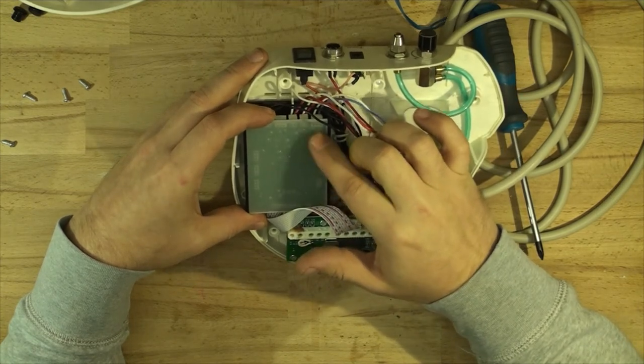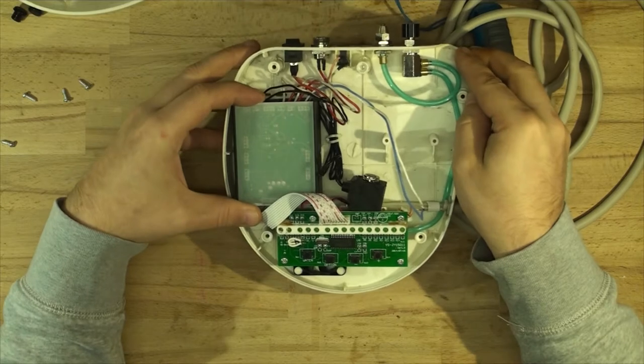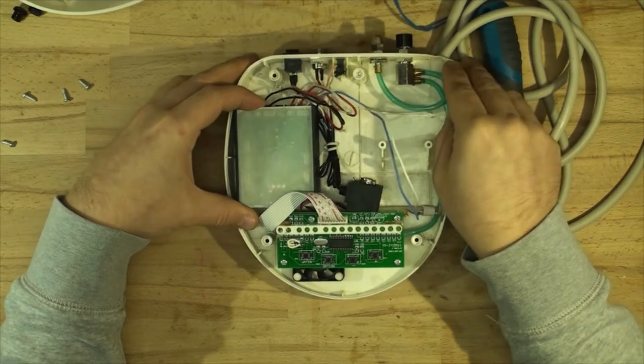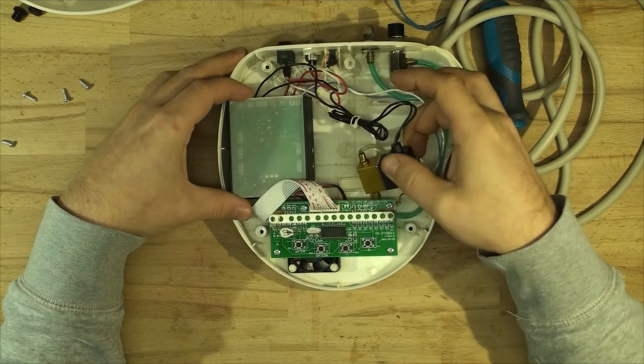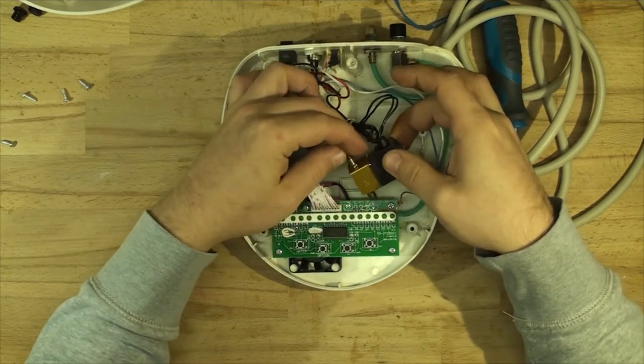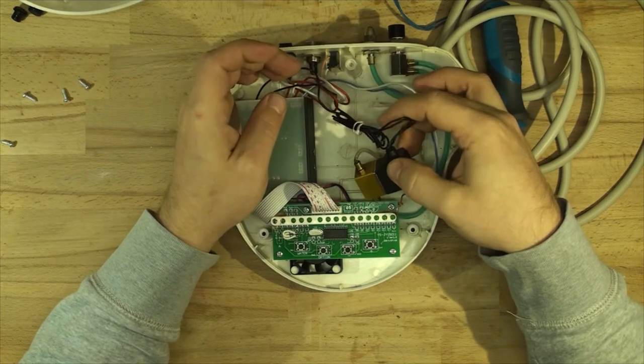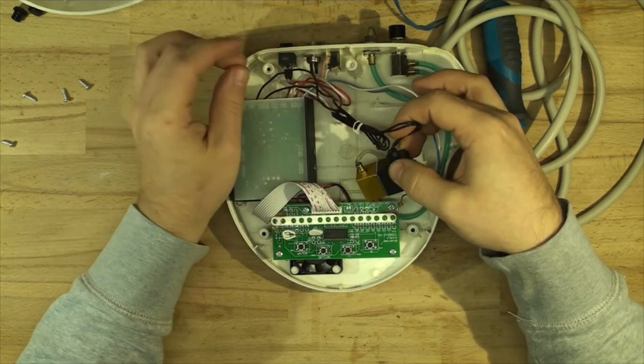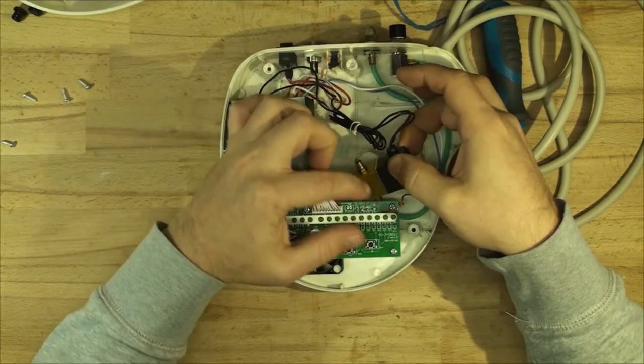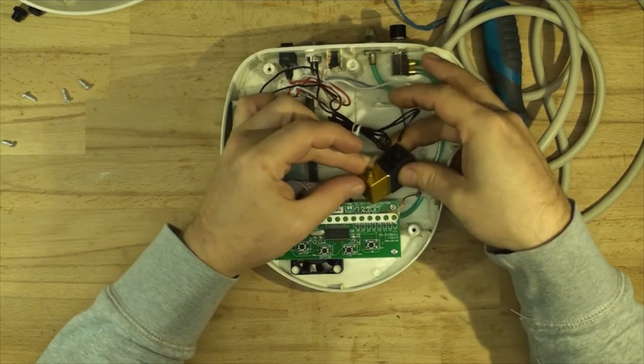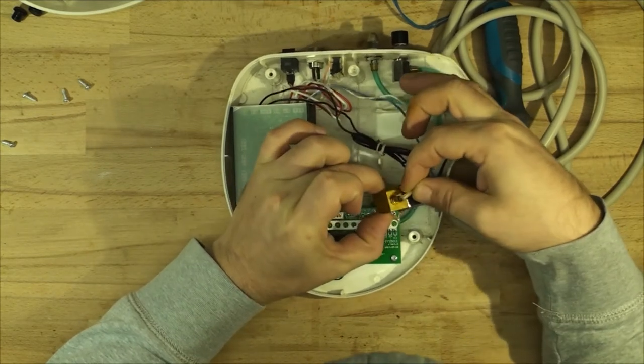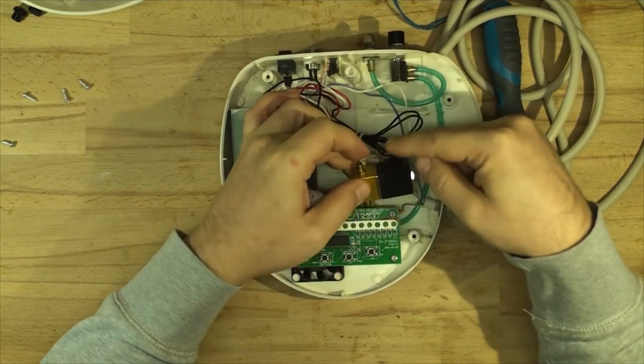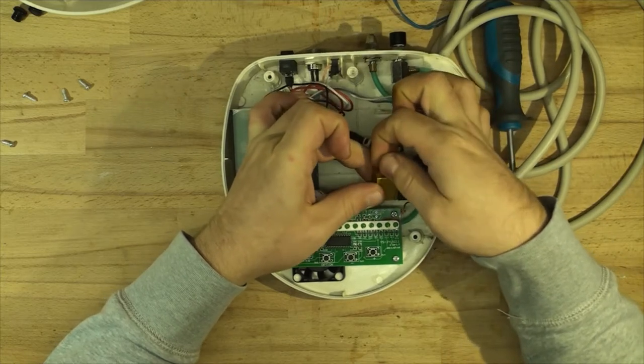I reckon it's about maybe 12 or 24 volts. How I will determine it: I'll look where the input is and where it goes to. If it goes straight to a capacitor, that means DC voltage. If through a bridge rectifier, that's AC. The next thing we're going to do is check this solenoid valve. Just blow in one side and see if it leaks. If it doesn't, apply power to it and see if it opens up.